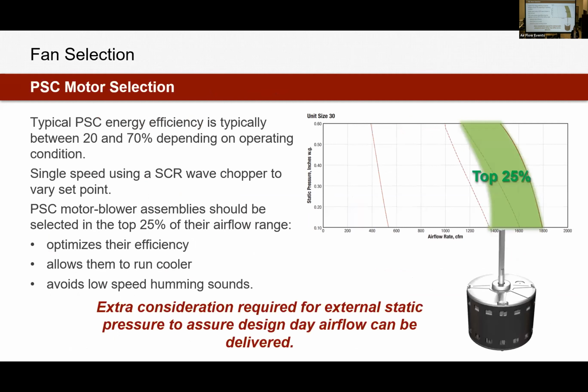So PSC motors only have an efficiency of 20 to 70%. They are more efficient at their top end. So if you're running it at its max range, the top 25%, then you're going to get to 70% efficiency. That is the highest amount of efficiency you'll ever get. If you are not running it in that top range, you're more like 20 to 50% efficient. The way a PSC is working is it's chopping down the electrical wave and turning it into heat. So you have a lot of heat loss with a PSC, which is where you're dropping your efficiency.